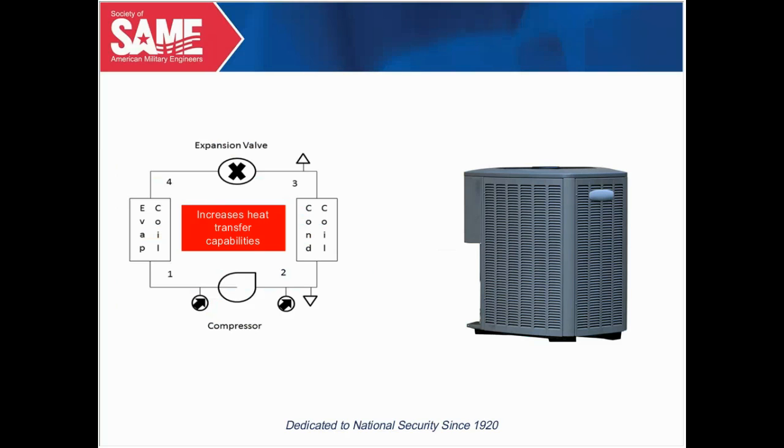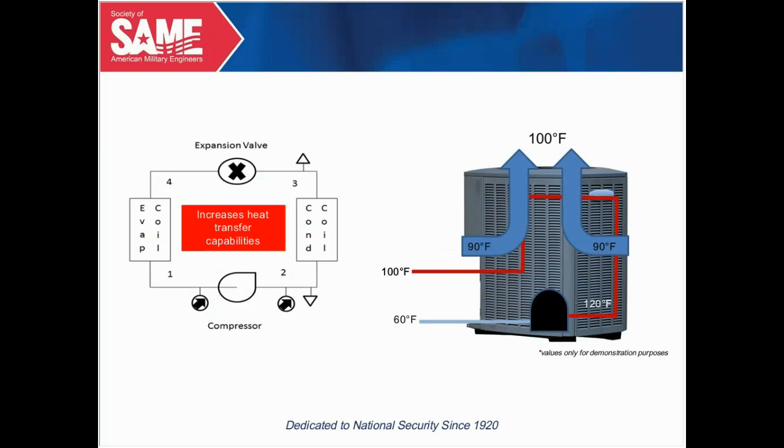So the way this essentially works is you have refrigerant flowing into the compressor, then into the condenser, and you have airflow going through that condenser coil, picking up that heat and rejecting the heat to the outside. If you spray a mist using this product, it will decrease that outdoor air temperature and essentially increase the capacity of the unit. And the theory is it will save up to 30% energy.